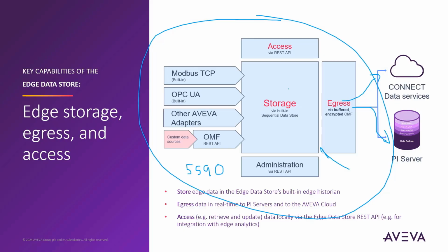Additionally, in terms of the service account that this entire application runs as, the installer creates a specific user account that this Edge Data Store service runs under. The account is only used for running the service. It can't be used for things like interactive sessions. It's not recommended that you configure or modify this service account, as it could cause undesirable operation of the Edge Data Store. The installer configures the binaries, configuration files, and all the data files so that they're only accessible as appropriate by the service account. It's not recommended you modify the permission or ownership assignments for any of those.